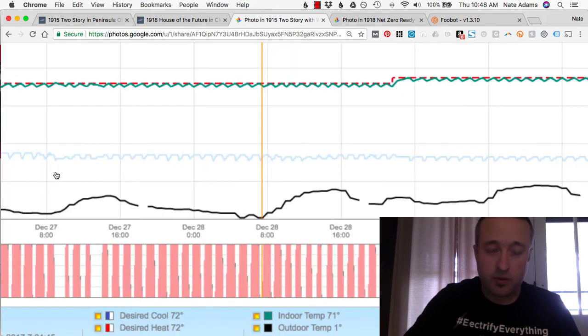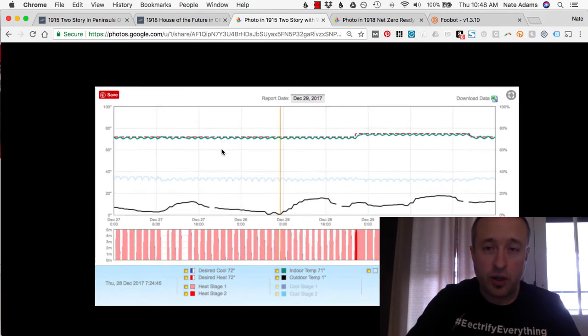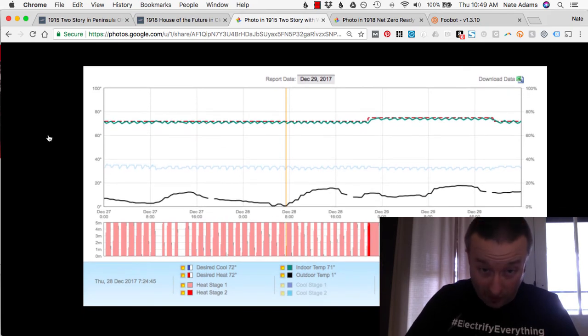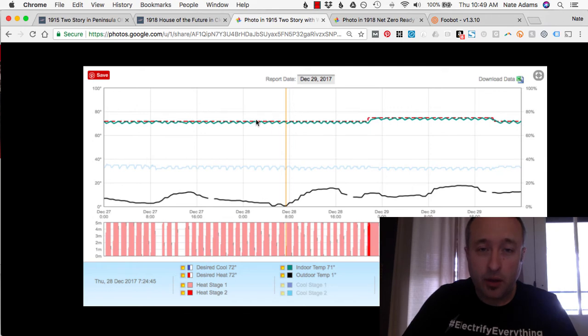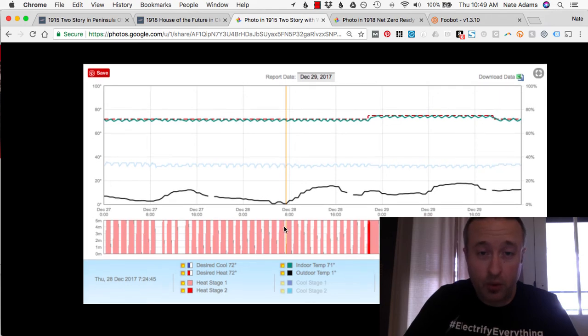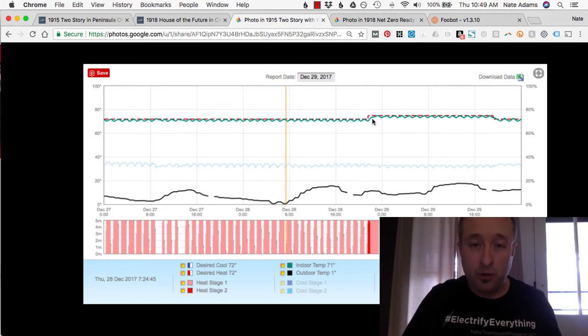And what we can do to get there, there's a couple of different tools. This is an Ecobee thermostat that we put in at Kevin's house. You can see the green line here, this is indoor temperature. You can see it up, down, up, down, up, down. And then the red dashed line behind it is what the set point is. So in this case, he has it set to 71 degrees. Down here you can see, 72 is what he has it set to, and 71 is what it's at. Outdoors, on this line here, it's very cold, it's 1 degree. But the important thing to look at is down here, these bars. The light red, this is a 2-stage furnace. Light red is first stage, dark red is second stage. So you can see that high stage was only used when he turned the thermostat up. And that created enough of a temperature difference that the furnace kicked into high. And it pretty quickly jumped the temperature, even though you can see it was still quite cold out. It was like 10 degrees outside.